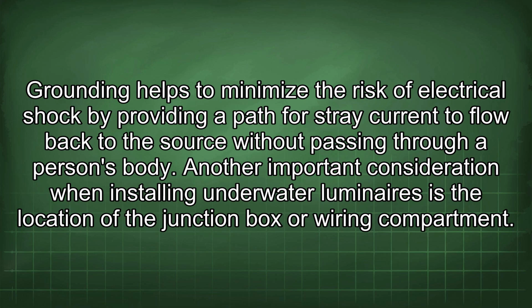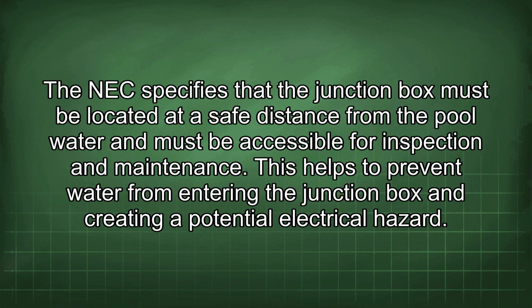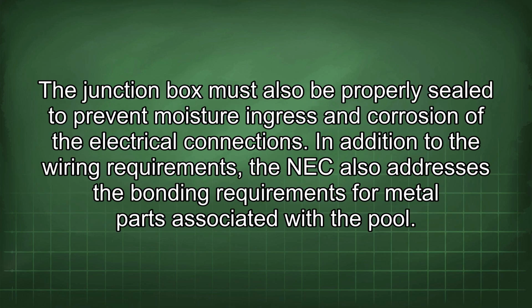Grounding helps to minimize the risk of electrical shock by providing a path for stray current to flow back to the source without passing through a person's body. Another important consideration when installing underwater luminaires is the location of the junction box or wiring compartment. The NEC specifies that the junction box must be located at a safe distance from the pool water and must be accessible for inspection and maintenance. This helps to prevent water from entering the junction box and creating a potential electrical hazard. The junction box must also be properly sealed to prevent moisture ingress and corrosion of the electrical connections.